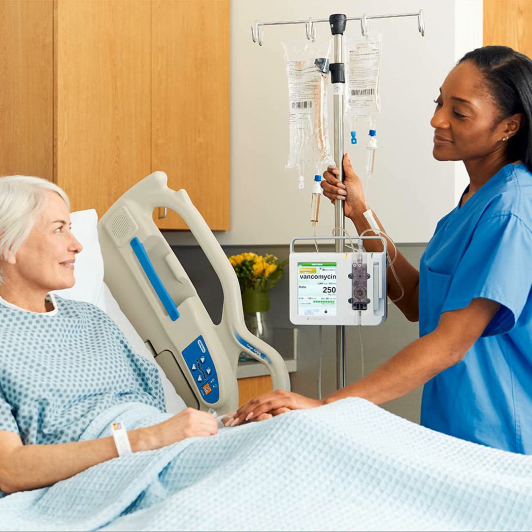Again, making this all easy for the nurse. A systems approach for infusion pump and tubing is that the priming and the loading of the tubing in an advanced pump should be easy. I'd say as easy as inserting a credit card into a reader. So you should not require a nurse to thread IV tubing through these very narrow channels, close little clips, close the door. Take that all away from the nurse. Actually, just make it as easy as that credit card into a reader.